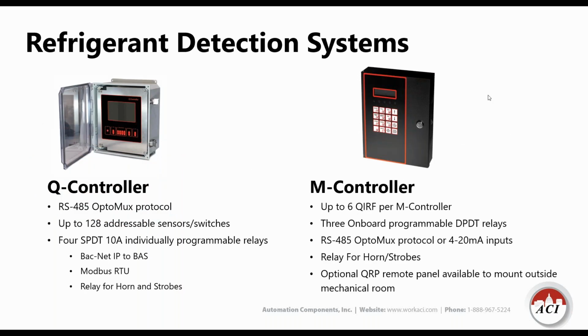Once again, here's the two controllers. 90% of the time, the systems we do will be set up with an M controller because we haven't seen too many chiller plants that use 6 QIRFs in one mechanical room. And like I said, the M controller comes with 3 relays, relays for horn and strobes, which I'll show you in a little bit on a network diagram.